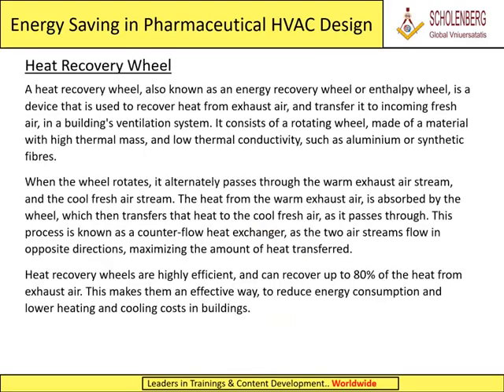Heat recovery wheel. A heat recovery wheel, also known as an energy recovery wheel or enthalpy wheel, is a device that is used to recover heat from exhaust air and transfer it to incoming fresh air in a building's ventilation system. It consists of a rotating wheel, made of a material with high thermal mass and low thermal conductivity, such as aluminium or synthetic fibers.